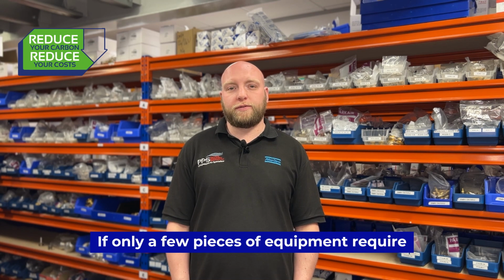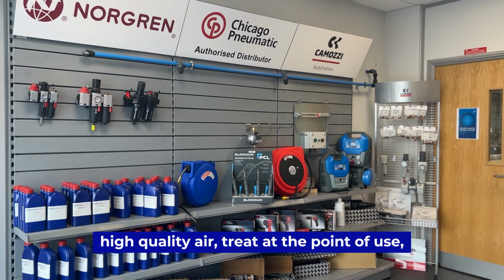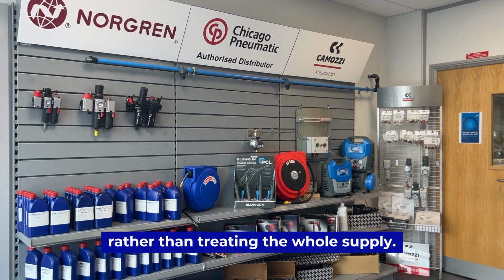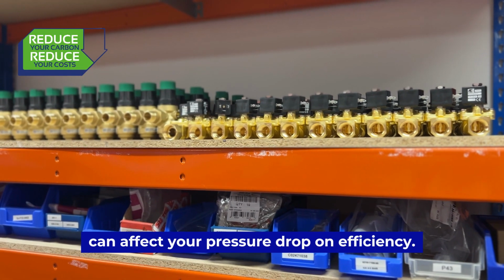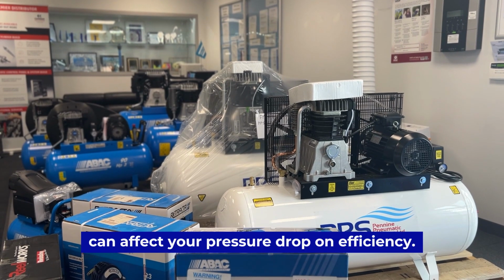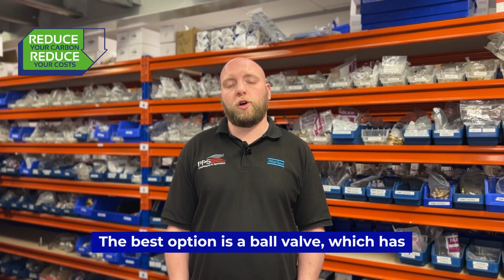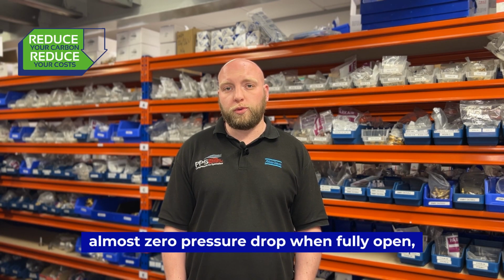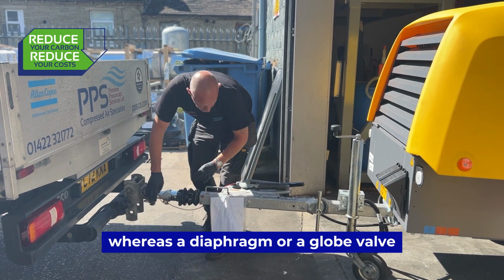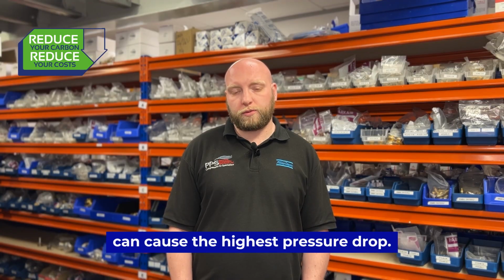If only a few pieces of equipment require high quality air, treat at the point of use rather than treating the whole supply. The type of valve you choose can affect your pressure drop and efficiency. The best option is a ball valve, which has almost zero pressure drop when fully open, whereas a diaphragm or a globe valve can cause the highest pressure drop.